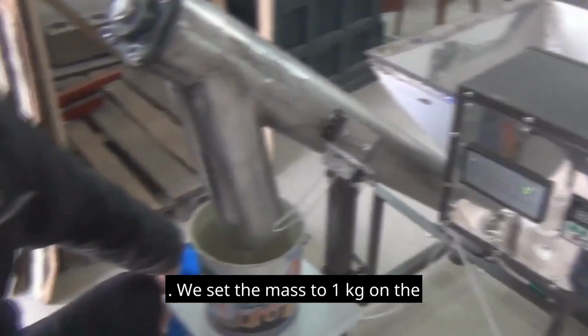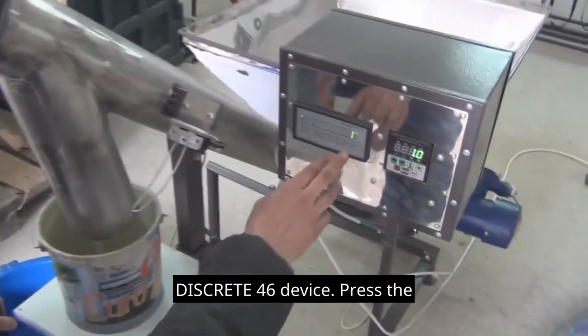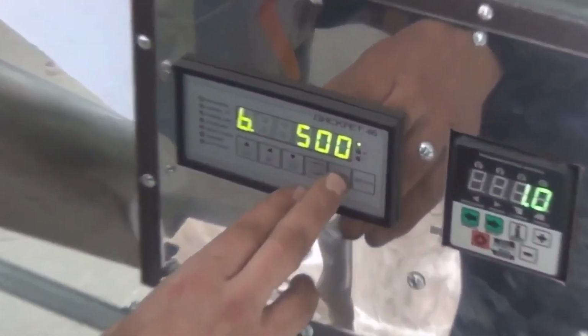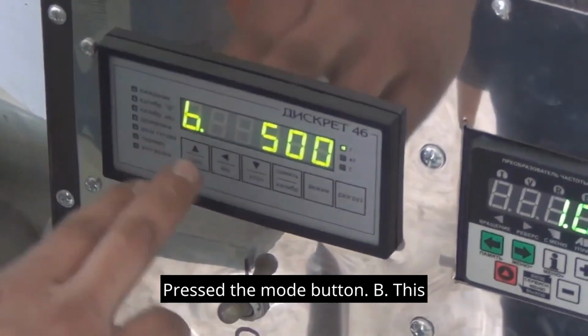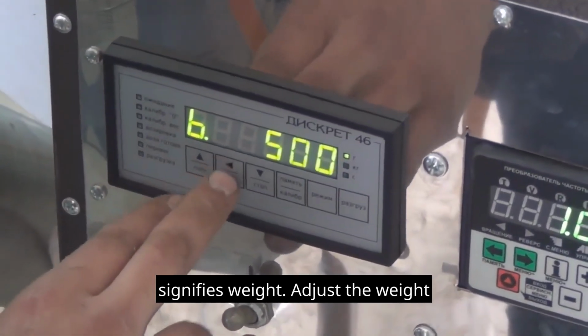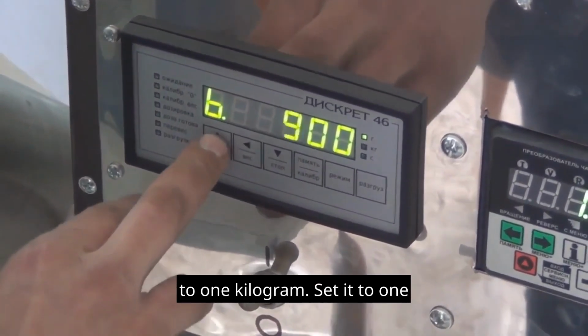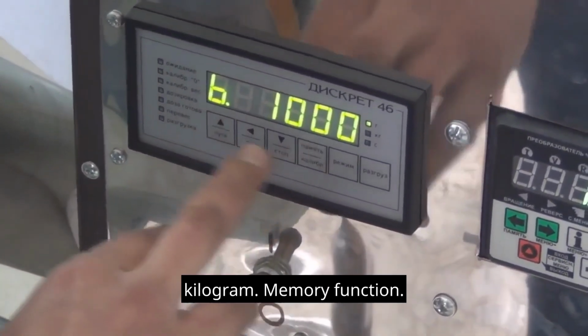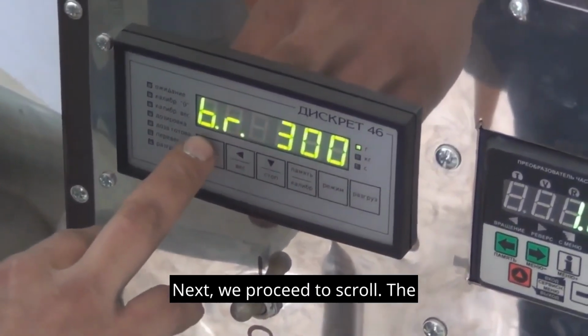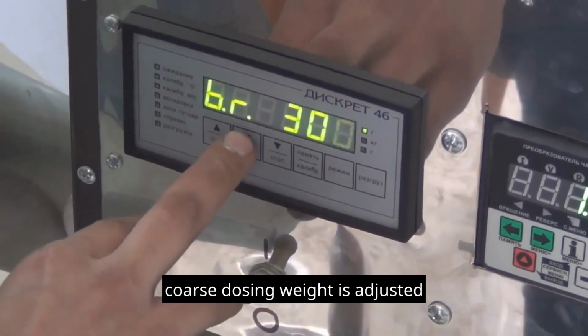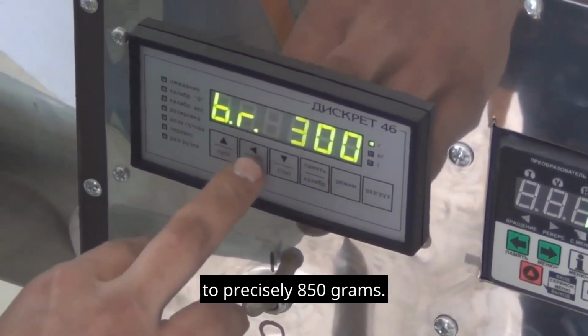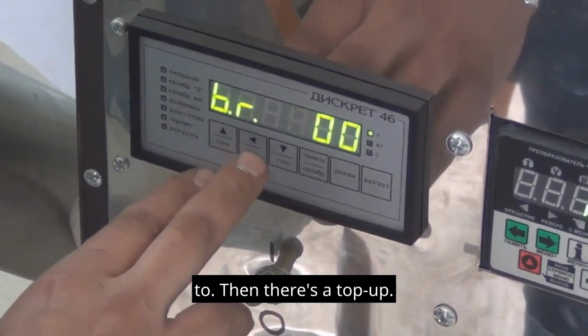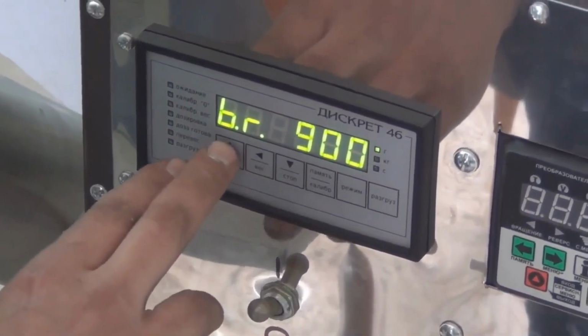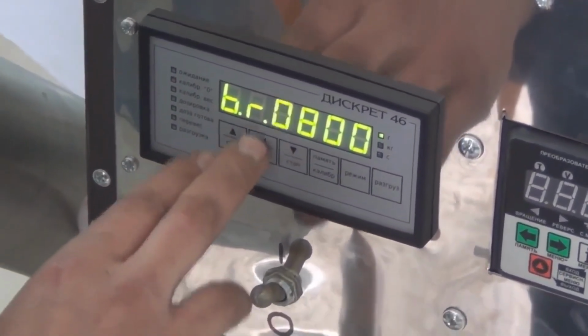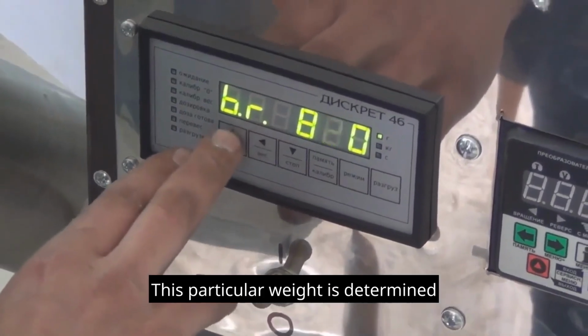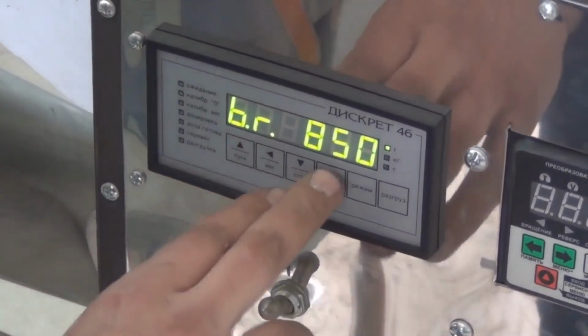Or, we set the mass to 1 kilo on the discrete device. Press the mode button. B signifies weight. Adjust the weight to 1 kilogram. Set it to 1 kilogram. Memory function. Next, we proceed to scroll. The coarse dosing weight is adjusted to precisely 850 grams. This is the weight it pours fast to. Then there's a top up. This particular weight is determined through experimental methods.